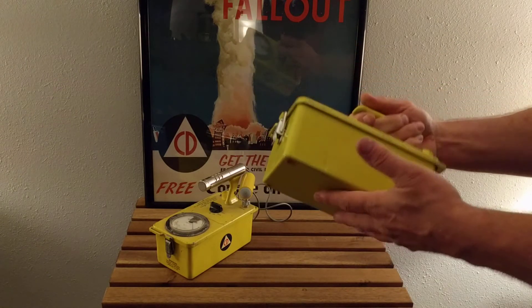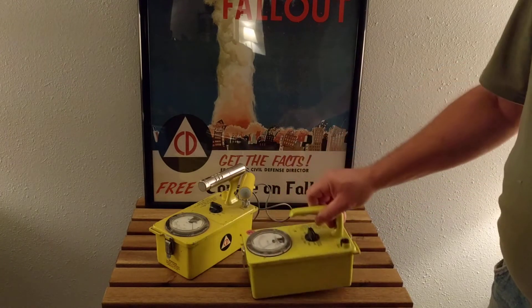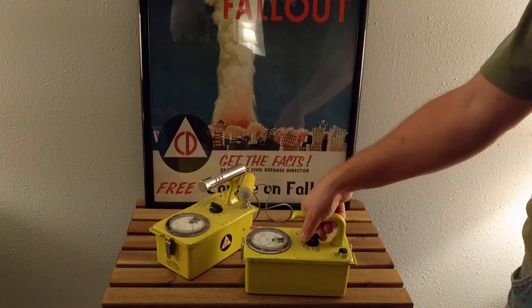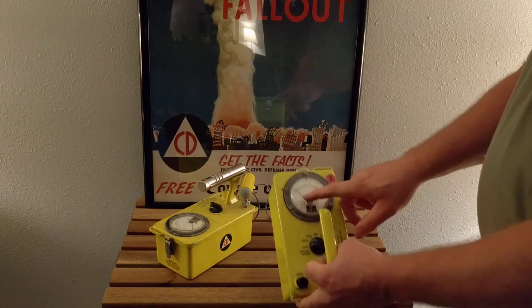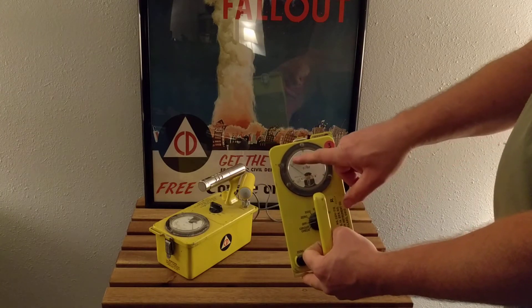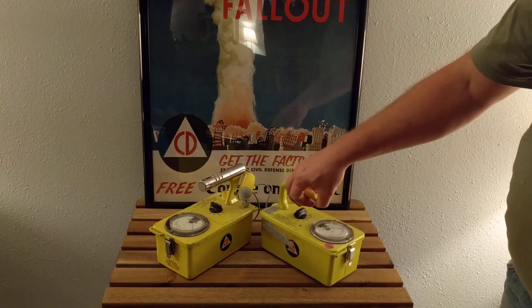These are usually broken because the electrometer tube has failed or it needs to be conditioned, and there are instructions online on how to do that. Basically you turn it on at the X100 scale and leave it there for 12 hours, then turn it off, then turn it on, and there's a specification of how high on the range it should go — only about two or three pips on the lowest, then up to one and back down on the highest. If it does any more than that, it's fried and it's no good.